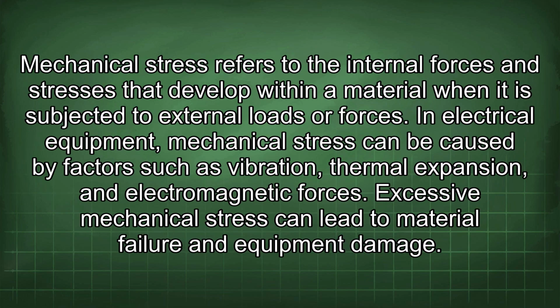Mechanical stress refers to the internal forces and stresses that develop within a material when it is subjected to external loads or forces. In electrical equipment, mechanical stress can be caused by factors such as vibration, thermal expansion, and electromagnetic forces. Excessive mechanical stress can lead to material failure and equipment damage.